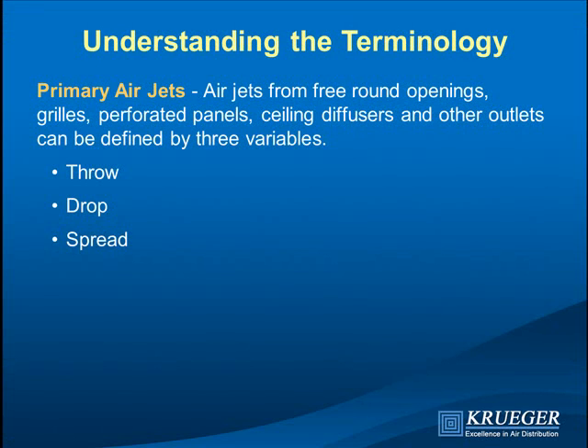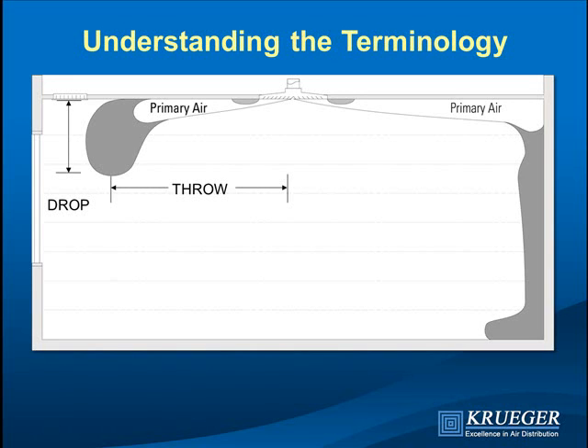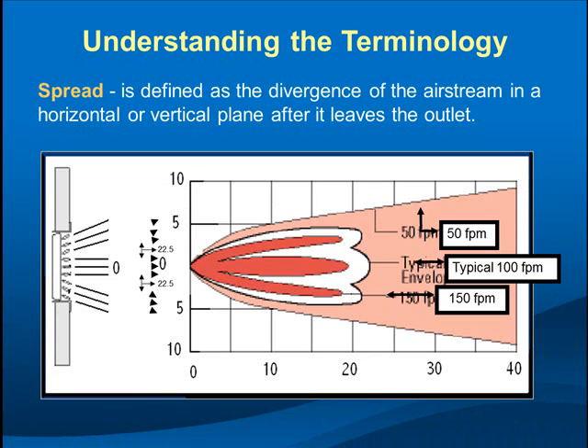Some of these terms appear in catalogs and some don't — I'll explain why. Throw is the distance from the center of the diffuser to a point where the velocity has slowed to a specified terminal velocity. Throw is meaningless unless you specify the velocity to which the jet has slowed. The jet slows because it induces room air; as the mass increases, the energy dissipates. We typically report throw at three velocities.